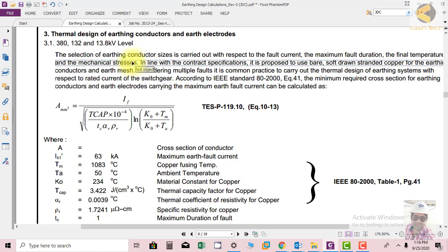One aspect is the current carrying capacity, another aspect is the temperature rise and thermal capacity, and the third, which is also most important, is the mechanical stress.